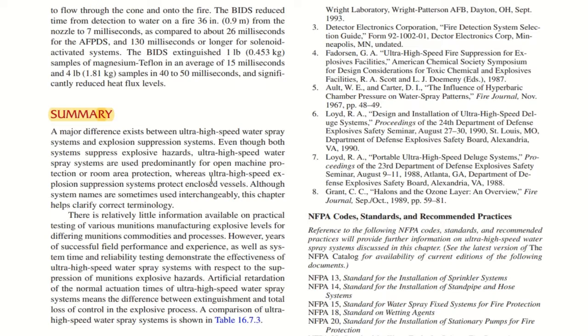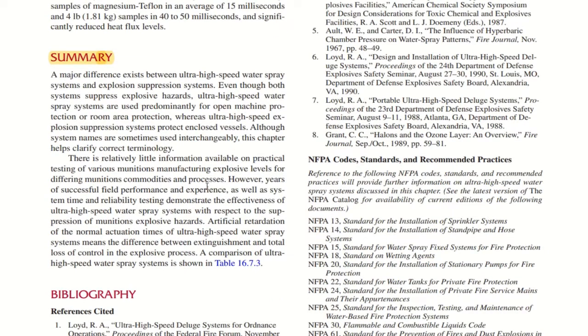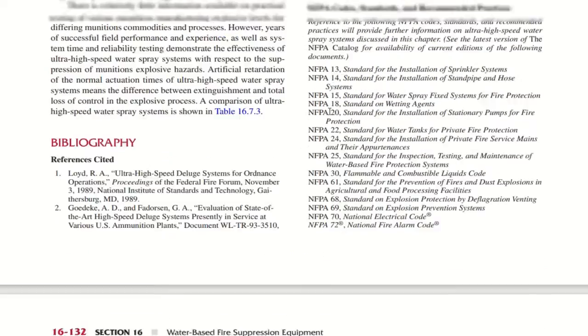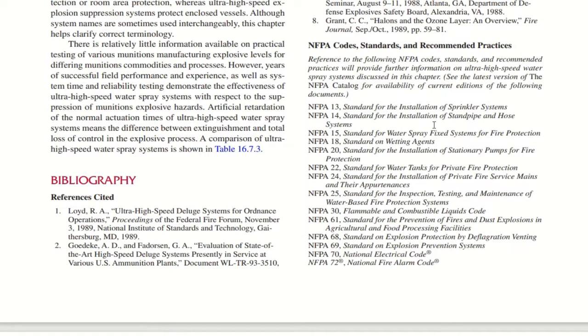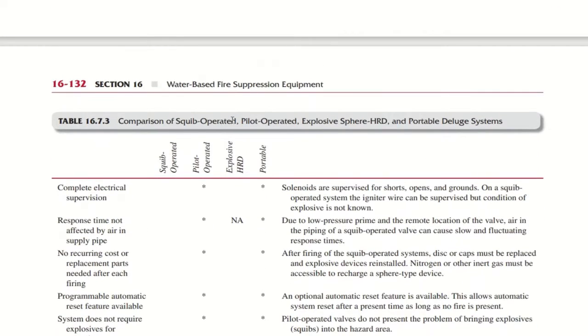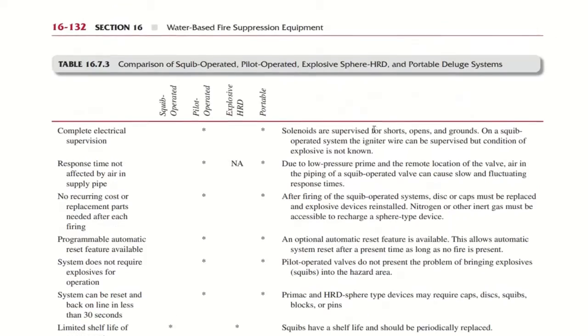A comparison of ultra high speed water spray systems is shown in table 16.7.3. So basically this chapter is referring to ultra high speed water spray systems and the classification of explosives. And you can see NFPA codes and standards here. NFPA 13 refers to the sprinkler system, 14 refers to the standpipe and hose system, NFPA 30 refers to the flammable and combustible liquids code, and so on. Here they have given a table comparison of squib operated, pilot operated, explosive sphere, HRD and portable deluge systems.